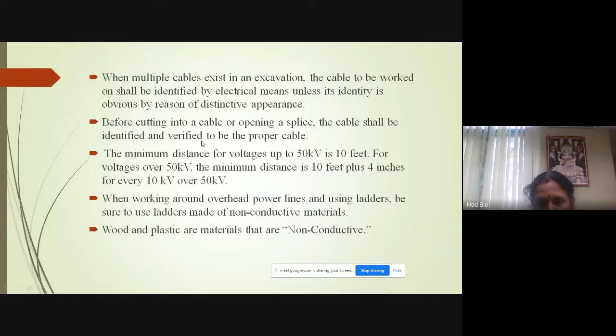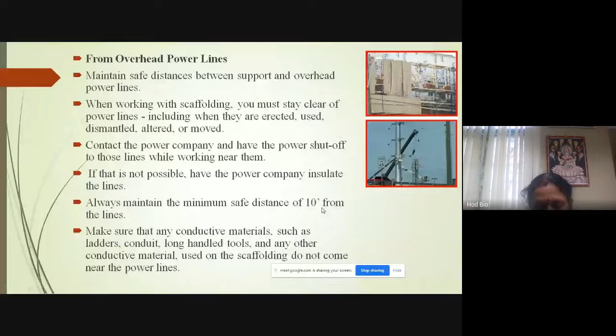The equipment will get spoiled before cutting into the cable or opening the splices. The cable shall be identified and verified as the proper cable. Okay, so here this is in a power station. Support overhead: maintain a safe distance between support and overhead power lines. Contact the power company and have the power shut off to those lines while working near them. If that is not possible, have your power company insulate the line. Always maintain a minimum safe distance of 10 feet from the line.